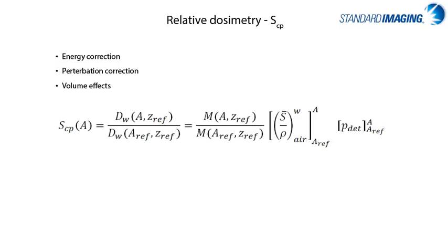Considering output factor measurements, it is important to select a detector that is appropriate so as to minimize the energy correction, perturbation, and volume effects, or at least have a dosimeter with known effects, which are often based on published peer-reviewed studies on the topic. This generalized equation shows the parameters that go into determining output factors when considering the ratioed measurements from the standard field, the stopping powers, and any perturbation effects.